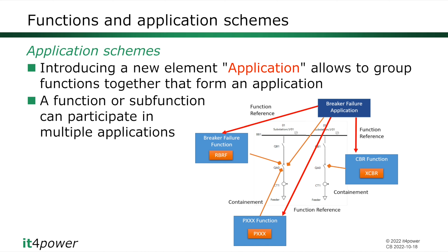The other element we introduce is application schemes. With the function and sub-function hierarchy, we can put functions in a hierarchical context, but a function may participate in multiple applications. For example, the breaker function shown here interfaces with the breaker and participates in the breaker failure application, but it may also participate in the tripping protection application, as well as in a control function doing a controlled operate of the breaker.